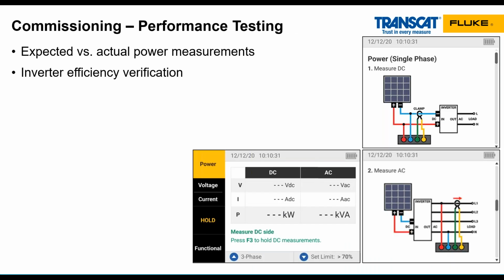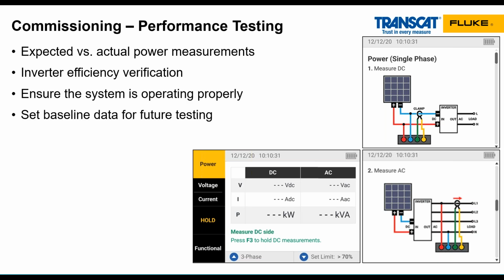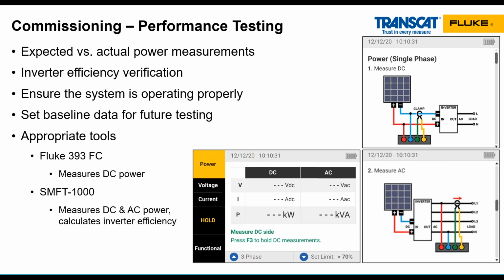At commissioning, we also do performance testing. This is making sure that the actual output of our system meets our expectations. It can also be used to test the efficiency of the inverter, making sure our system's working right, setting a baseline for the future so that we know the system was operating right when we commissioned it. We have a couple tools that can do this. The primary one is the SMFT 1000, which is what these screens on this slide picture.